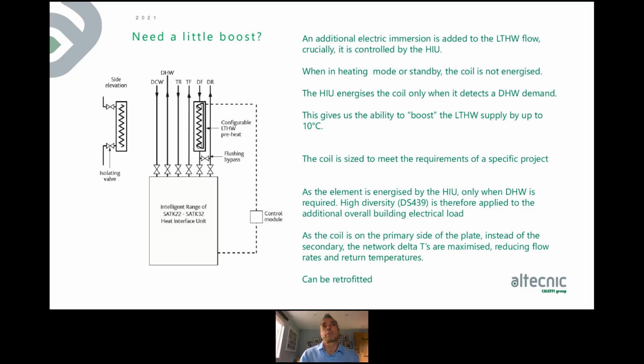So you can now have a primary flow or district flow that is below the temperature that you actually want on the hot water side. Because say if you're coming in at 45 degrees C, getting a really good COP from your heat pump, we can lift that to 55 instantaneously by the electrical energy into here. And then the HIU can produce your hot water at the right 50 degrees temperature with enough output.